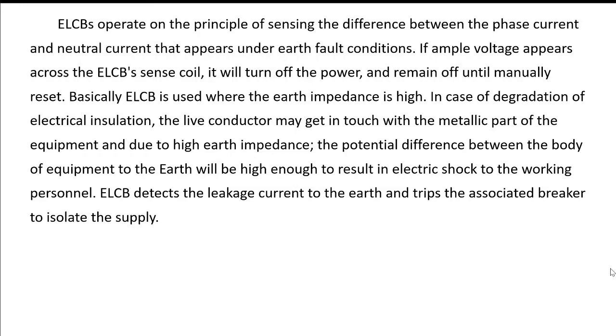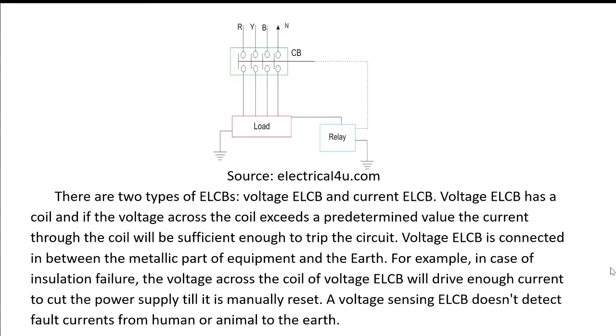In case of degradation of electrical insulation, a live conductor may get in touch with the metallic part of the equipment, and due to high earth impedance, the potential difference between the body of the equipment and the earth will be high enough to result in electric shock to the working person. ELCB detects the leakage current to the earth and trips the associated breaker to isolate the supply. There are two types of ELCBs, voltage ELCB and current ELCB. Let us discuss one by one.